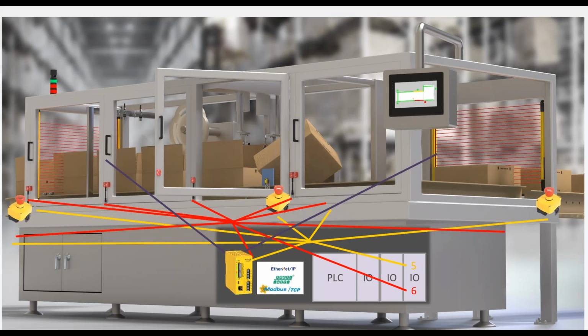That's a good question. So if we go back to this machine, what they're doing in this case is there's one primary hazard inside the machine. So whether a door opens or the light curtain is tripped, they're going to stop the hazard. The e-stop, so that's one zone. And before, when we had all these relays, the reason they had 3 different relays for that single safety zone is because of how relays are designed. The first light curtain has its own independent relay. The second light curtain has its own independent relay. It's just how they work. And then the door switches, because they're set up differently, have their own relay, but they're all tied together to turn off the same hazard. And then the e-stop circuit is used to kill power to the entire machine because something else has happened, an unexpected issue, and someone pressed an e-stop and it's turning off the entire machine.